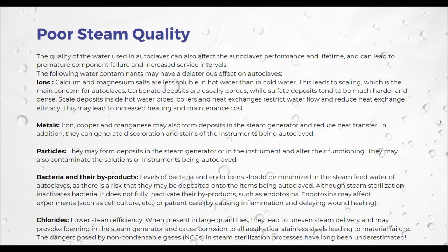The quality of water used in autoclaves can also affect the autoclave's performance and lifetime, and can lead to premature component failure and increased service intervals. The following water contaminants may have negative effects on autoclaves. We have ions, metals, particles. All of those we can have. We will have deposits in the steam generator or in the instruments, altering their functions. They may also contaminate the solutions or instruments being autoclaved. We'll also find that your pipes and heat exchangers will block up, which restricts water flow and causes more problems.